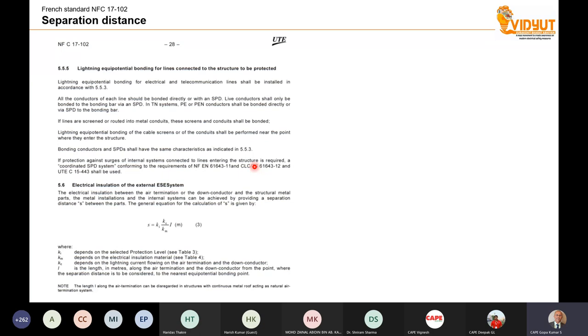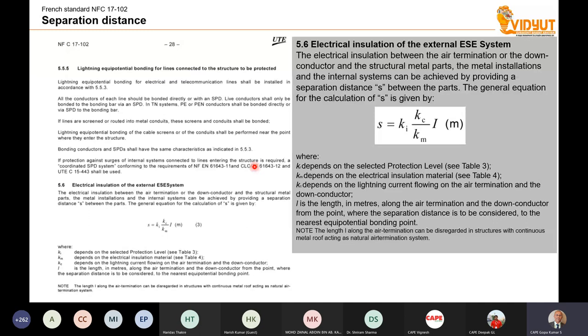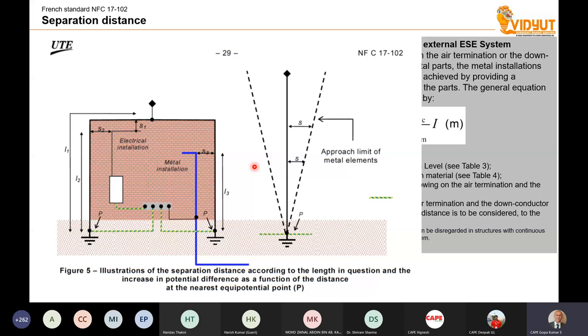Similarly, another subject explained in the French standard is electrical insulation, or separation distance. I explained what is explained in the Indian standard in the previous slide. Now the same calculation is also repeated in the French standard. So your electrical appliance and your down conductor system, or your ESE system, has to have a certain separation distance.